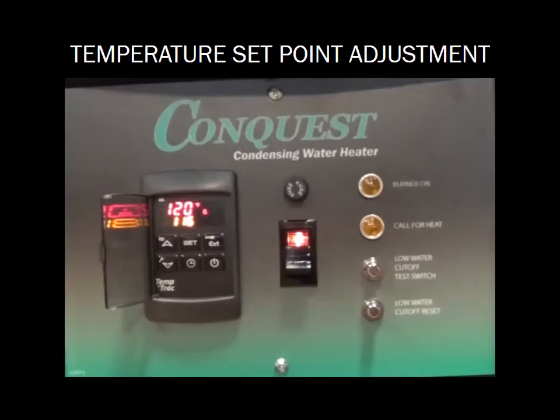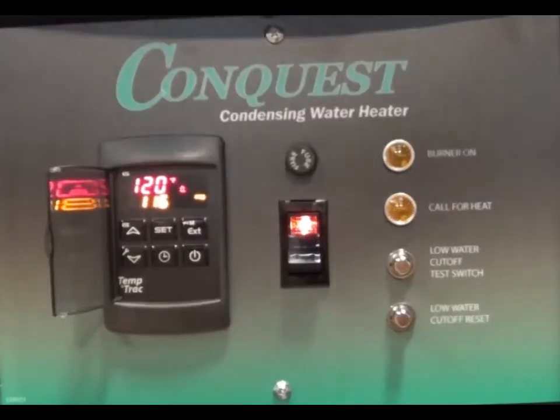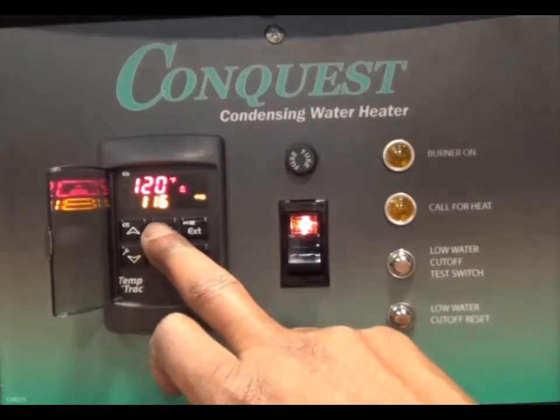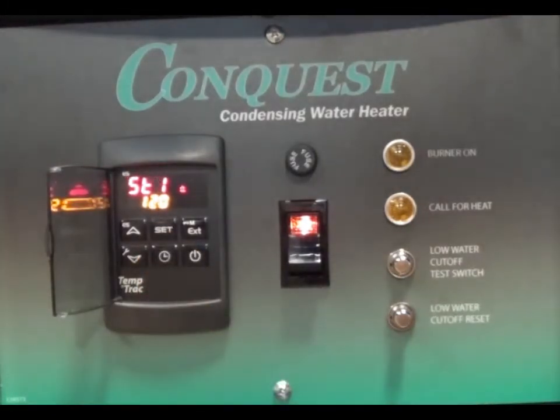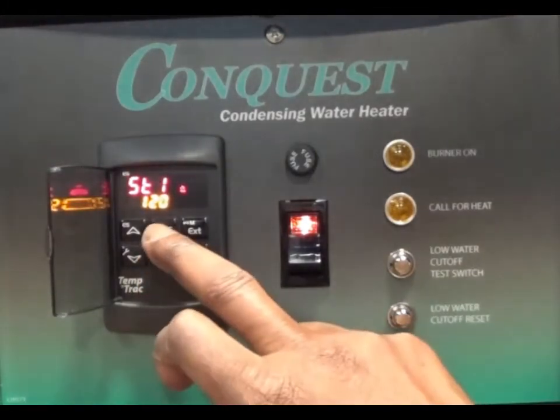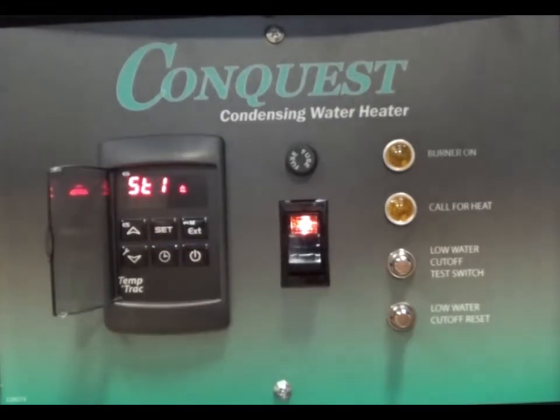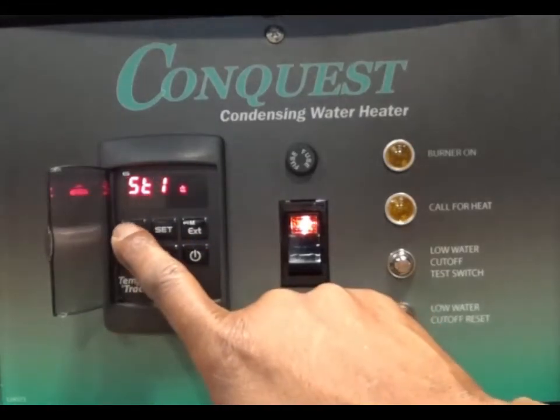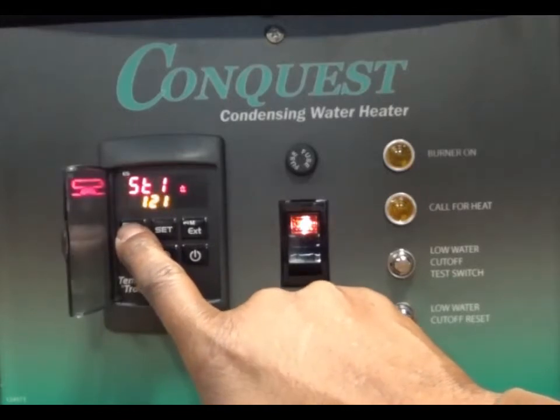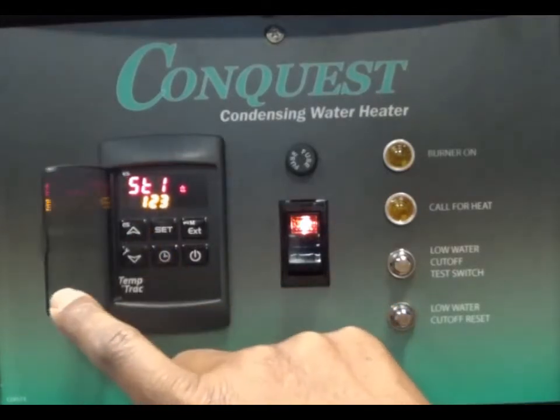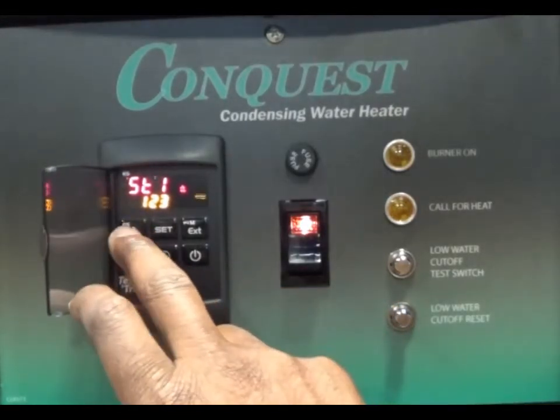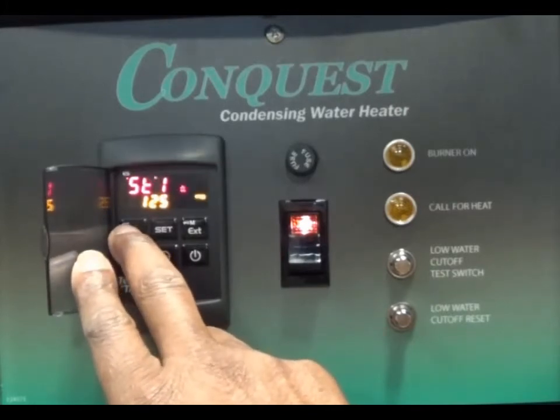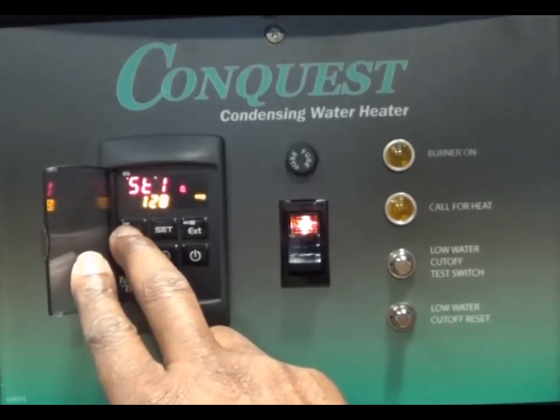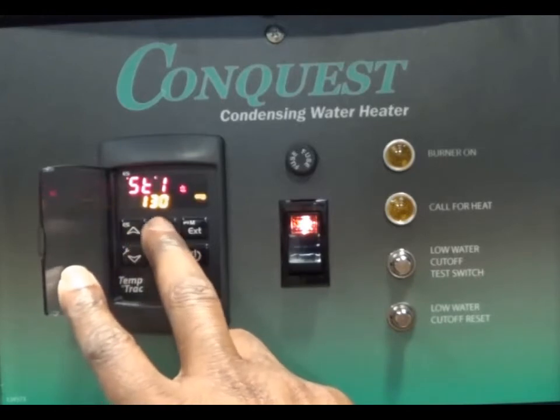To change the temperature set point, begin by pressing the Set button to display the current set point value. The parameter ST1 is shown along with its value. Press the Set button again to change the value. As the value flashes, use the up or down arrow buttons to increase or decrease the temperature set point. Press the Set button again to confirm the new value. To exit and return to the home screen, press the Set and up arrows together or wait 15 seconds without pressing any key.